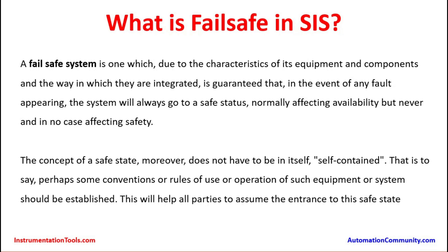The safety systems are designed and engineered in such a way that they always take care of plant safety. In case of any hazardous event, they take action and shut the respective valves and equipment to ensure the plant is kept in a safe operating condition. The plant operation may stop and production may go down, but safety is ensured. This is the most critical point while designing a safety instrumented system.